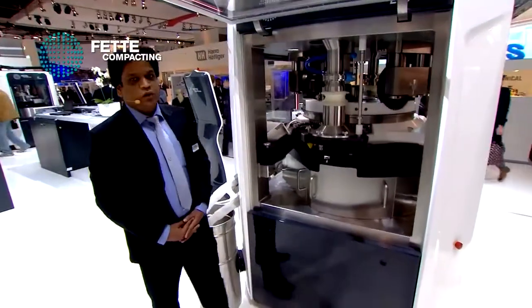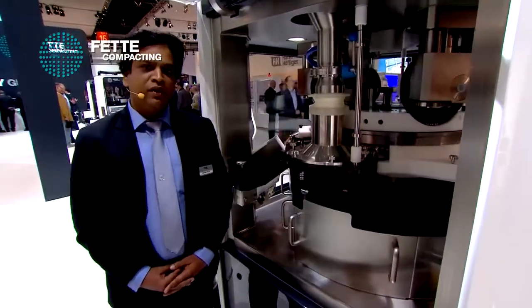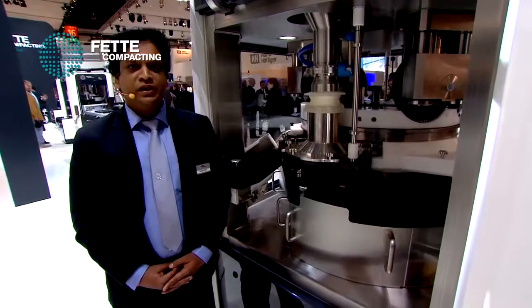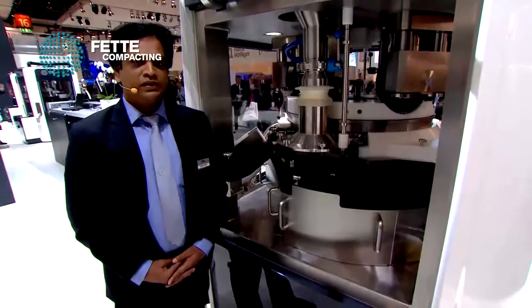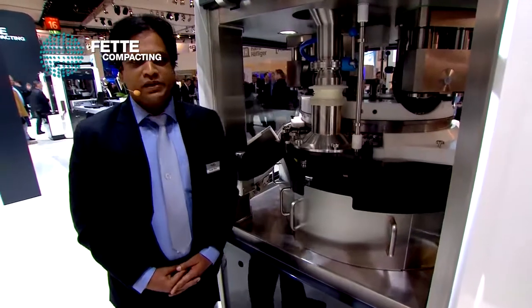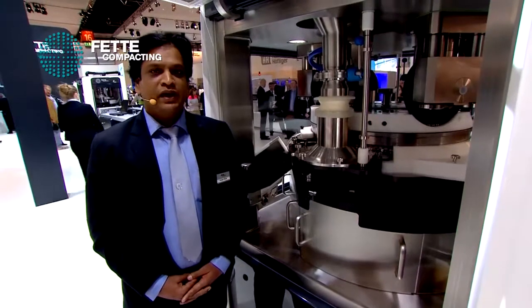Second, as direct compression molecules are increasing, we can use four compression stations in series — that means pre-compression, intermediate 1, intermediate 2, and main compression — gaining 166% dwell time. The third and most important function is that, since it's a double-sided rotary press, it can also make a bilayer tablet in the most controlled and secured way.